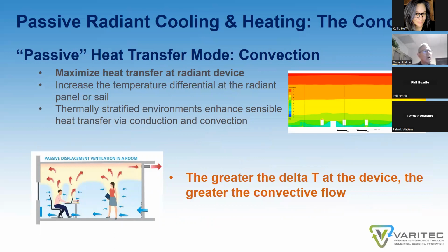So how do we make sure that we get maximum heat transfer at a radiant device mounted in a ceiling? Well, you want to make sure you maximize the temperature differential of the room air adjacent to that panel or sail. And to do that, you create a thermally stratified environment. By creating a greater delta T at the radiant panel or sail, you actually allow for more sensible heat transfer at that device and a greater force of convection. So thermally stratified environments are optimal for getting the most effective use out of a passive radiant solution.